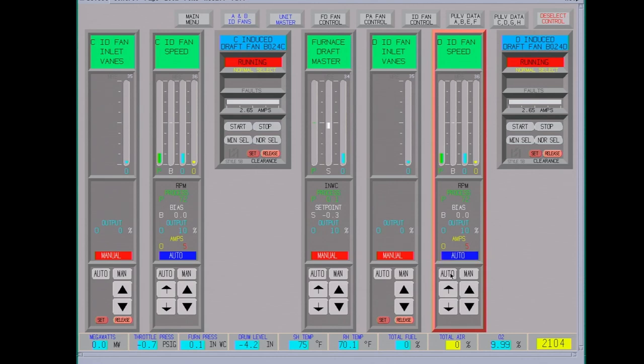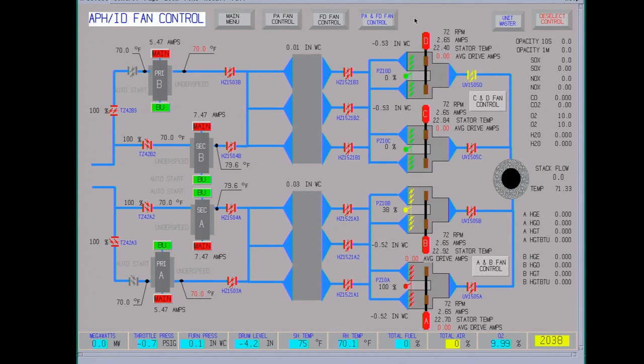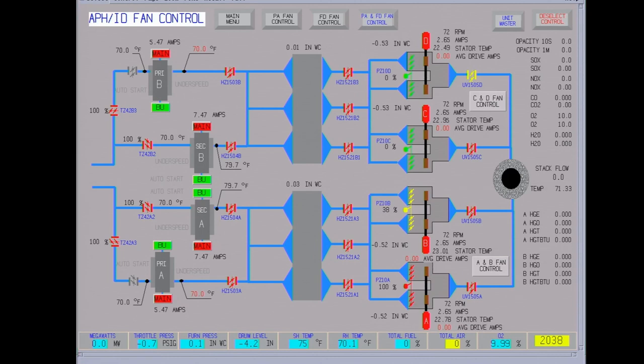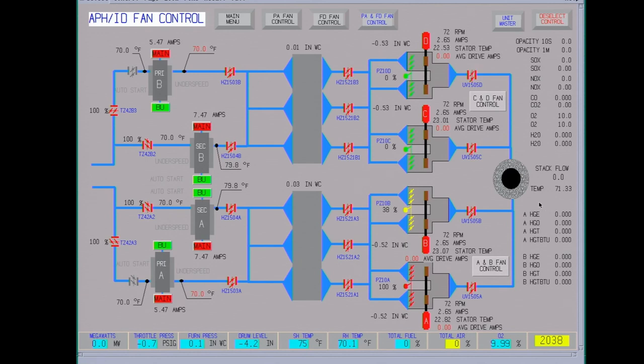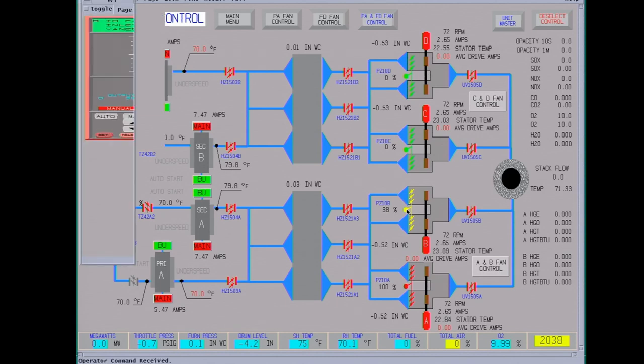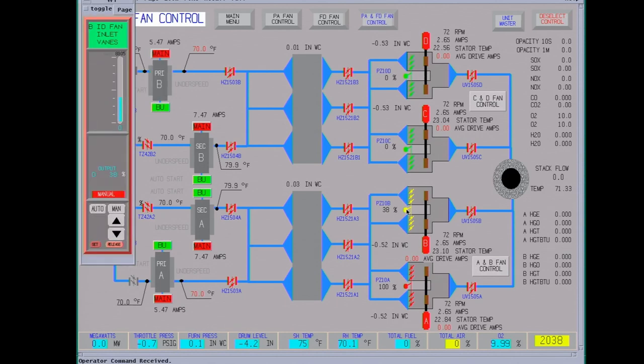Okay, normal select allows the fans to be in control now. The dampers drove closed once you put one in normal select. The other ones try to close in case you're just running one fan, so the flue gas system won't go here and recirc back around. These are always ran manually open.